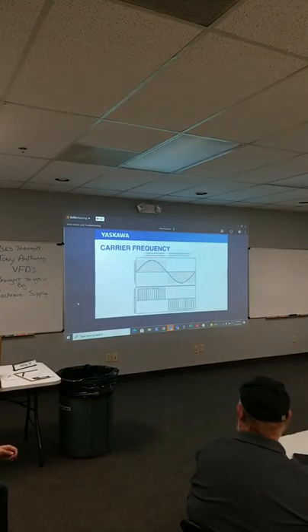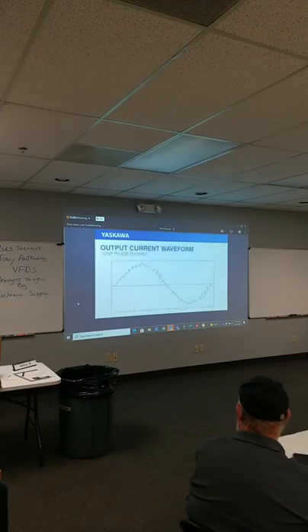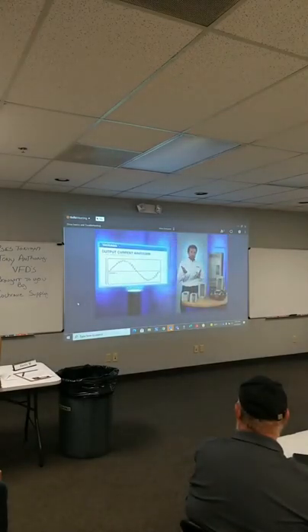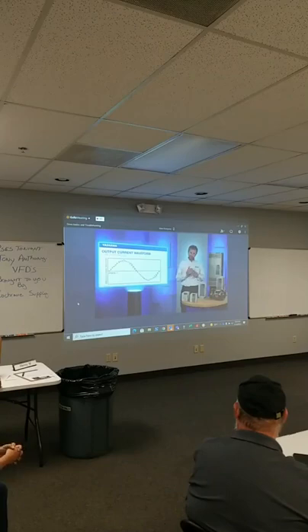You can see how the fundamental output frequency reference in blue reflects onto the actual output via this given carrier frequency. But we are finally brought to the output current wave for a given phase. As you can see, this looks sinusoidal. Well, remember that an induction motor is basically an elaborate inductor. And what do inductors mainly care about? That's right, current. The drive is sending the motor a relatively nice and clean sine wave so it can do its job, which is to turn a shaft and produce work.